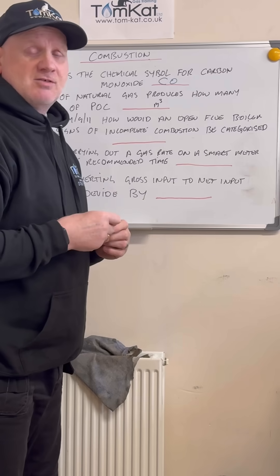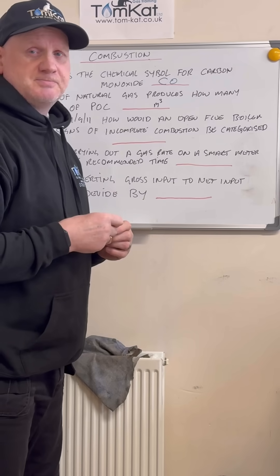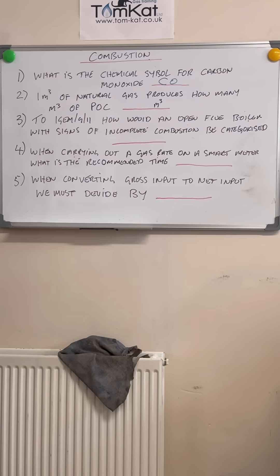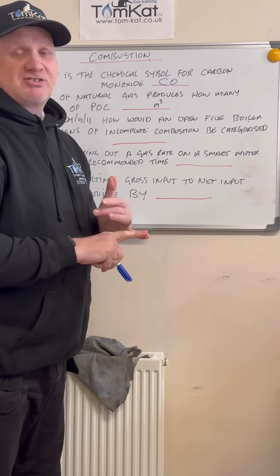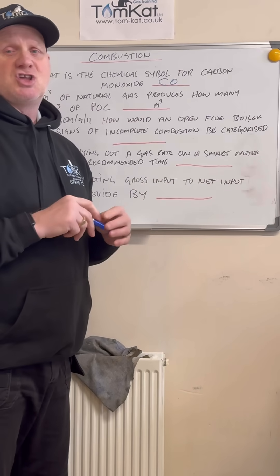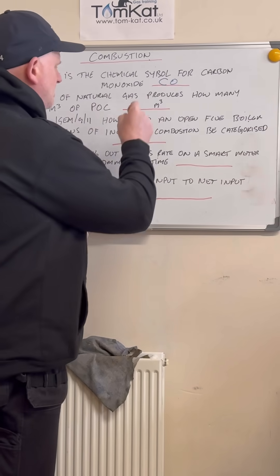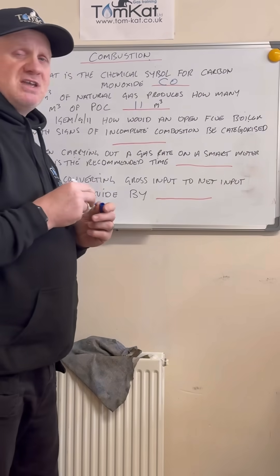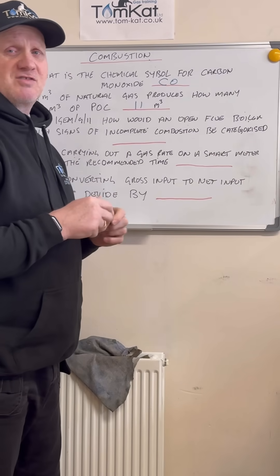Let's have a look at question number two. One metre cubed of natural gas produces how many metres cubed of products of combustion? Well, every one metre cubed of natural gas requires 10 metres cubed of oxygen or thereabouts, so it produces 11 metres cubed of products of combustion.